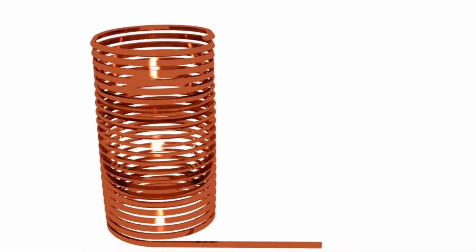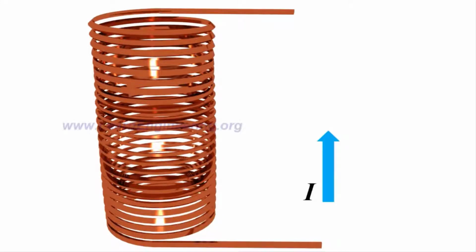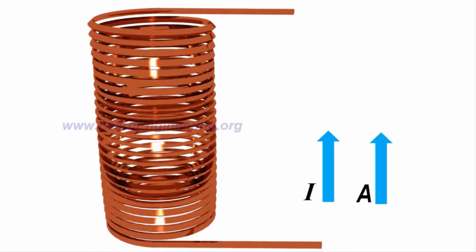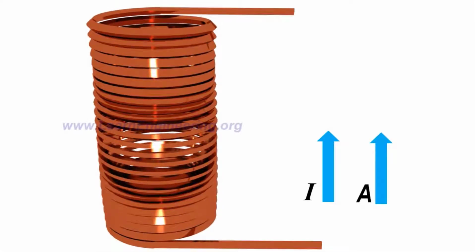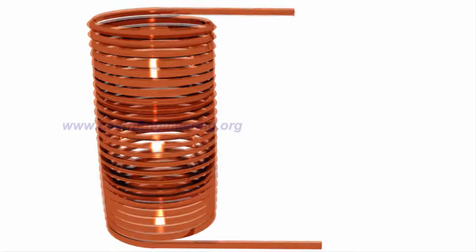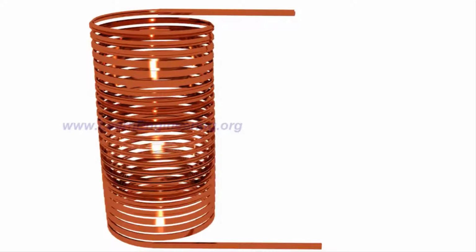But as the current to be handled becomes larger, the complexity of such windings increases. A large current requires a large cross-sectional area. Thus, eddy current loss also becomes high. For this reason, two or more conductors connected in parallel have to be used to reduce eddy current loss. The modern practice is to use a continuously transposed cable.